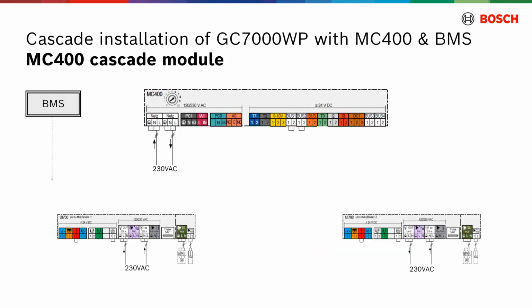It is very important to ensure the correct polarity when connecting the BMS to the 0 to 10 volt terminal. The connections are as follows. 1 is ground, 2 is 0 to 10 volt input for heat demand from the building management system, and 3 is 0 to 10 volt output, optional, for feedback.